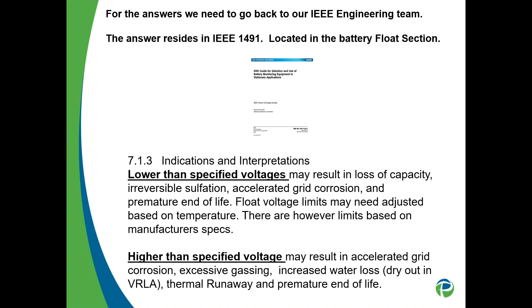So voltage is very important, and we can go back to all of our IEEE standards that talk about how to protect your batteries. Like it says in IEEE 1491, if you have low voltages, you're going to have sulfation occurring, an accelerated corrosion rate, and a lower runtime or capacity. And if you have higher voltages, you potentially get the same thing: accelerated grid corrosion, gassing, thermal runaway, and again, a premature, lower service life.